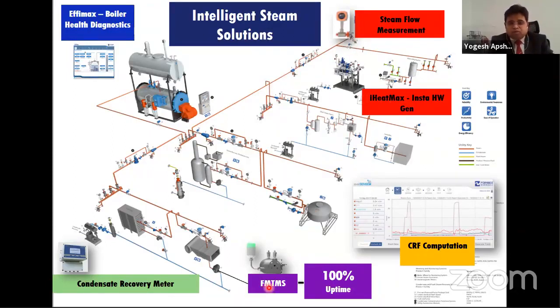Then the FMTMs, which is a trap monitoring system, for the critical traps, where we can monitor the uptime of the steam traps. Then the condensate recovery factor computation: how much condensate recovery is possible in the plant and how much the plant is doing. And the condensate recovery meter, which measures the condensate going back to the feed water tank. So all these digital inputs coming to the same platform will make a complete steam system truly intelligent.